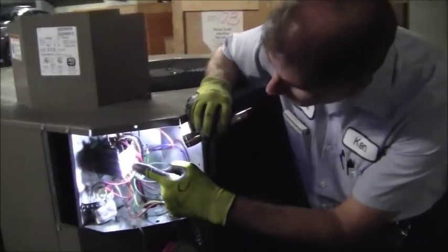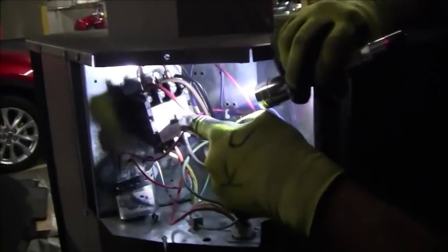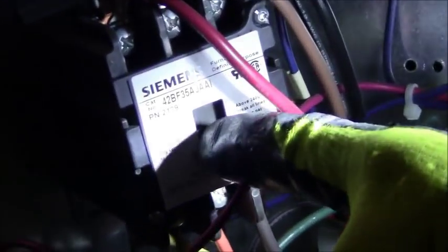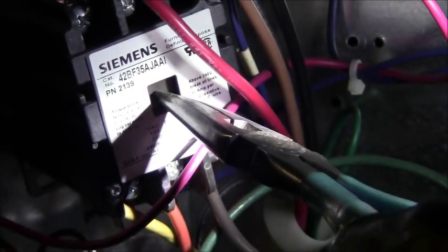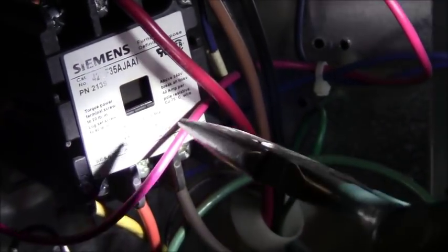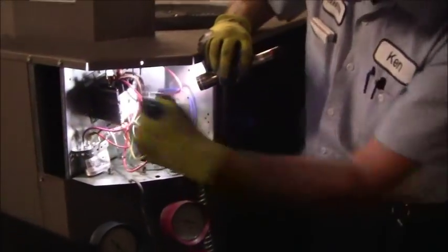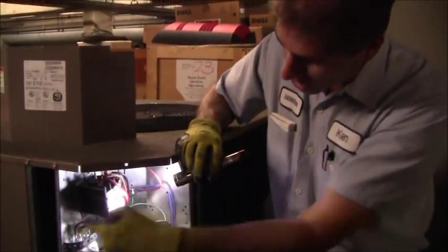Okay, when you're looking at the contactor, this portion right here that's like a little square in the middle is an indicator to tell you that the contactor is physically pulled in. Hypothetically, if it wasn't pulled in, I could take these needle nose pliers and push that in by hand. But right now, I can tell you that there's 24 volts going across the coil, which is pulling that in. So this is pulled in, and you don't have anything going on. The next thing I wanted to do was investigate the power going to the unit.